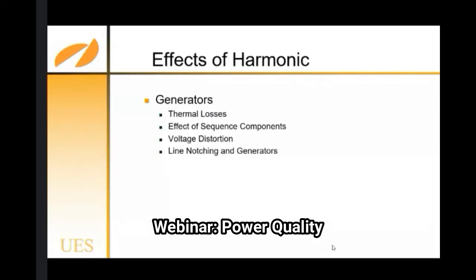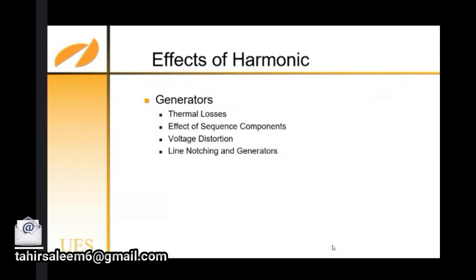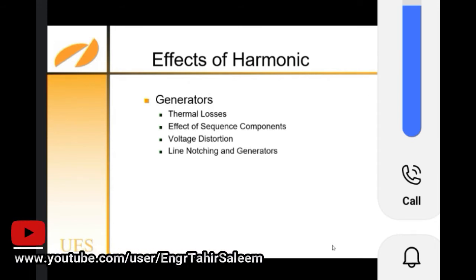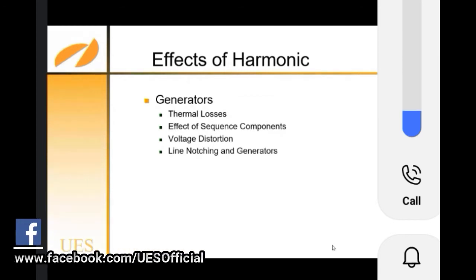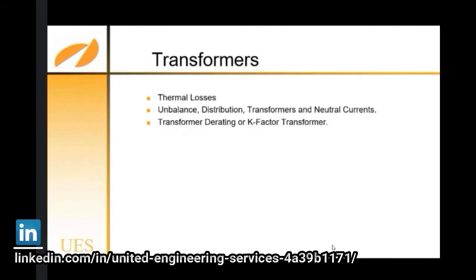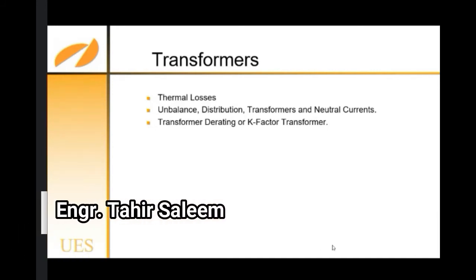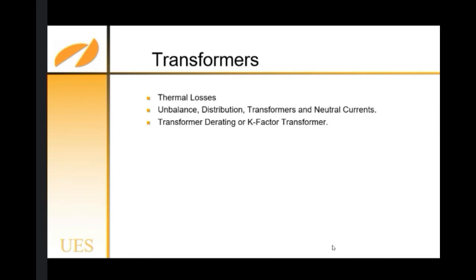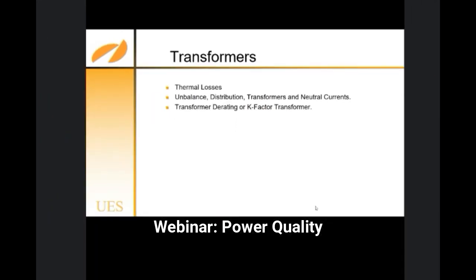The thermal losses will increase in generators. Effect of sequence components, unnecessary tripping, voltage distortion, line notching, and generally in generators the AVR gives you a lot of problems if there are a lot of harmonics. Transformers: you will have an increase in thermal losses, unbalanced distribution, neutral currents, transformer derating or K-factor transformers. Generally for transformers, the design parameters will have to be changed. If an environment has harmonics, the K-factor should be considered in the selection of the transformer.